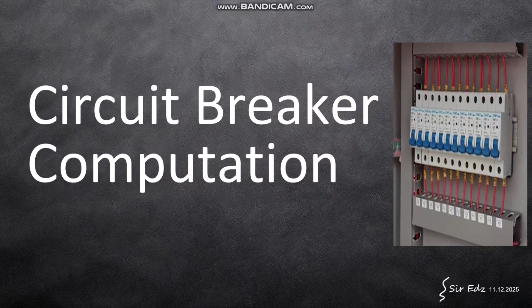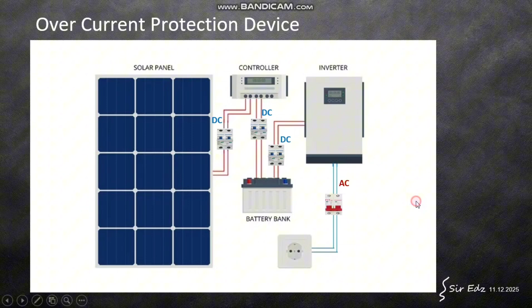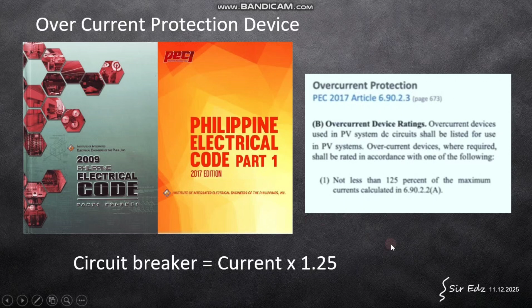So we have this system here. Typically, we need to compute the three DC breakers and one AC breaker. How are we able to compute that? We have a formula: circuit breaker equals current times 1.25 safety factor, based on the Philippine Electrical Code.